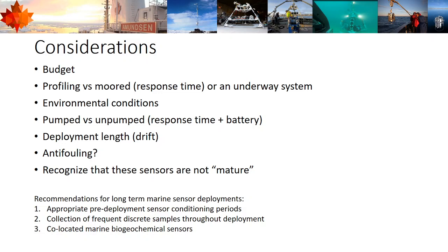So your response time is going to be a little bit slower, you're going to be consuming battery, and that's something to consider if you are reliant on a battery source that is directly connected to the instrument and you're not cabled and don't have to worry about that stuff. So building that battery budget.